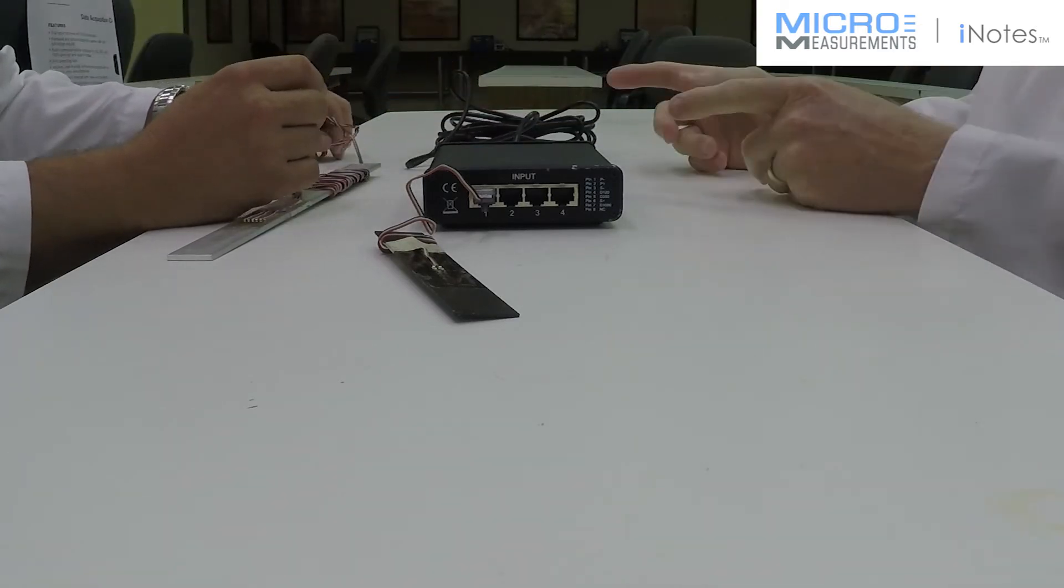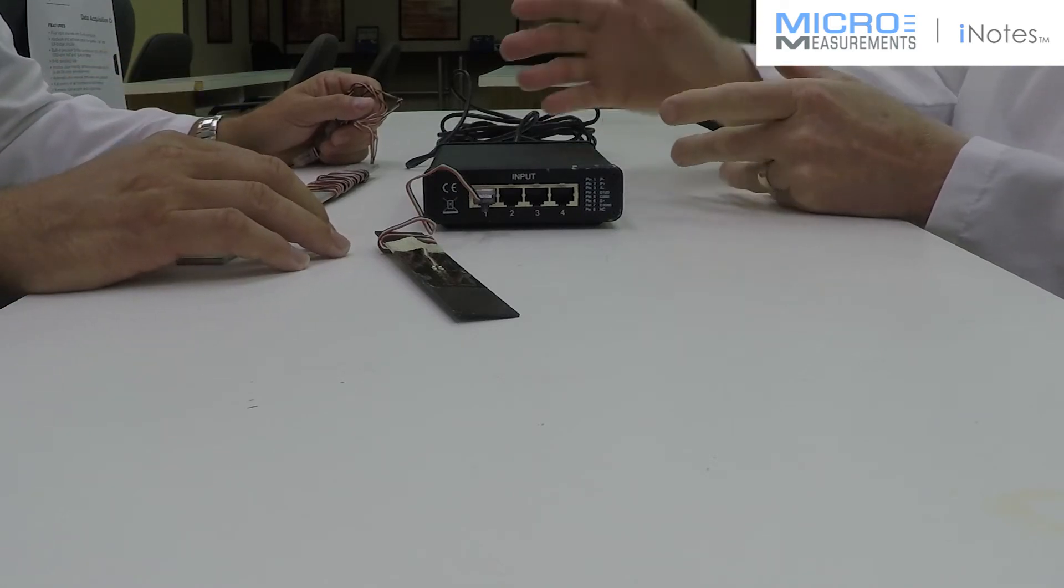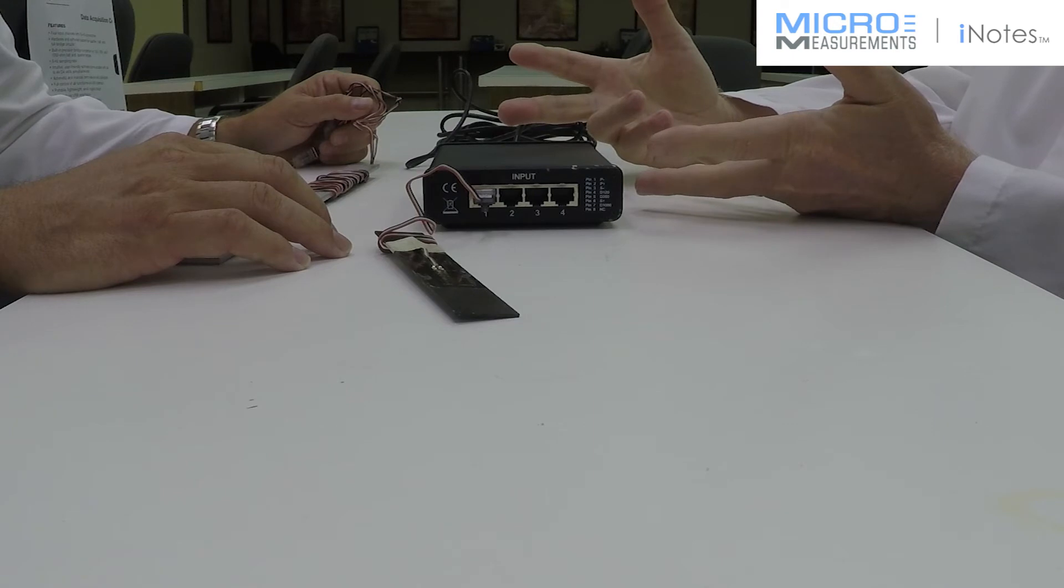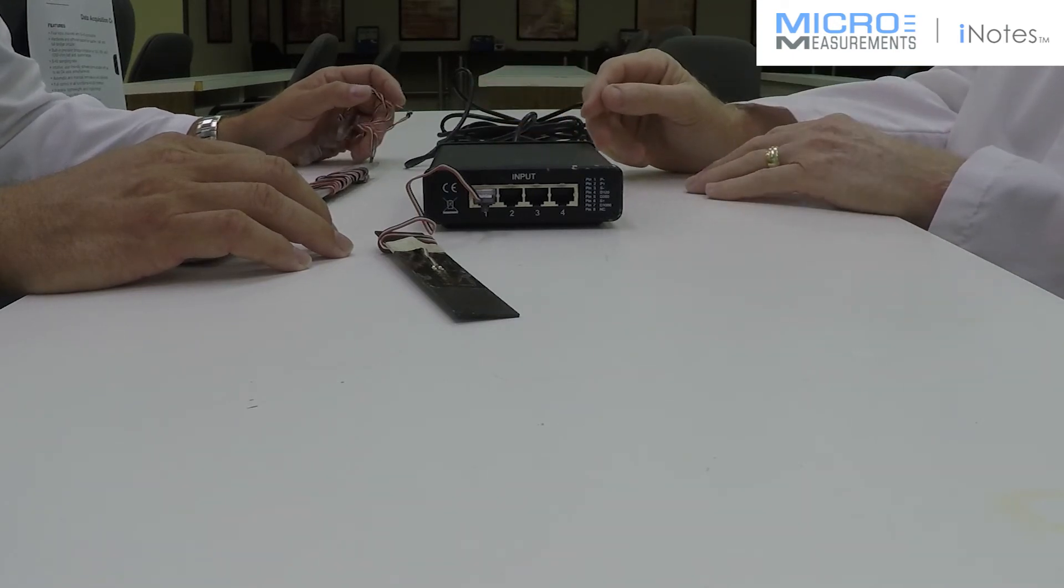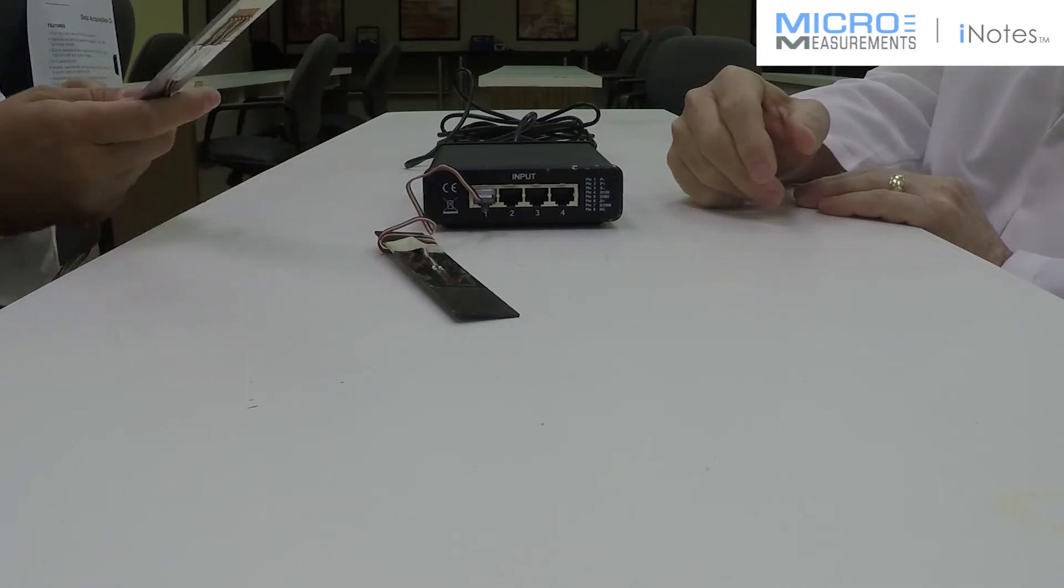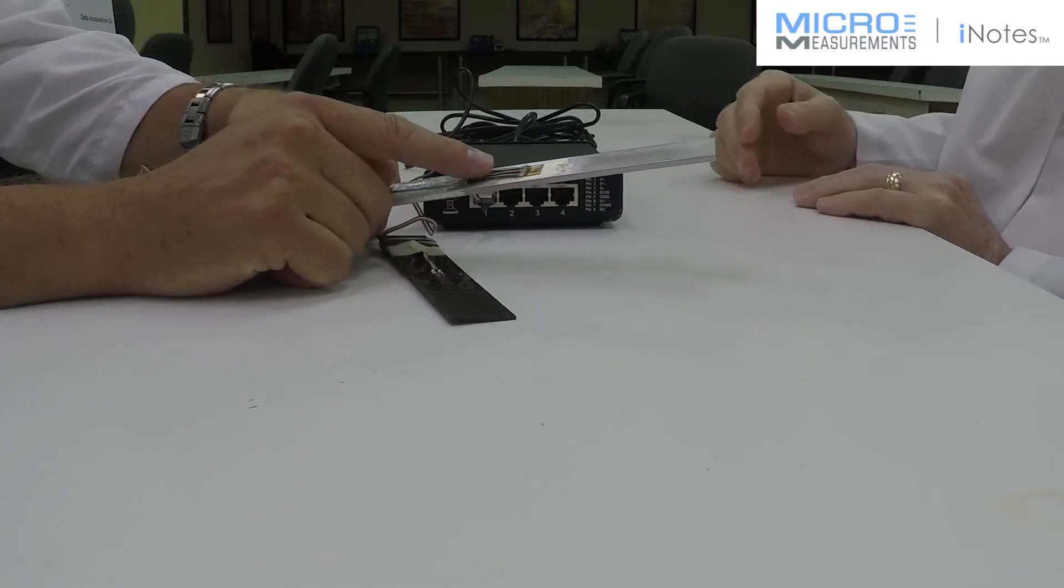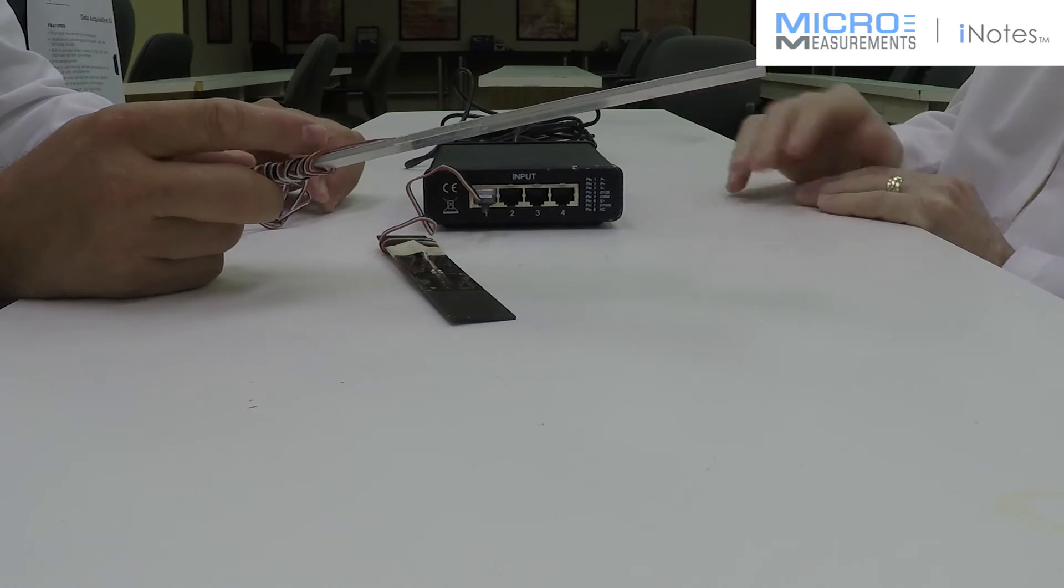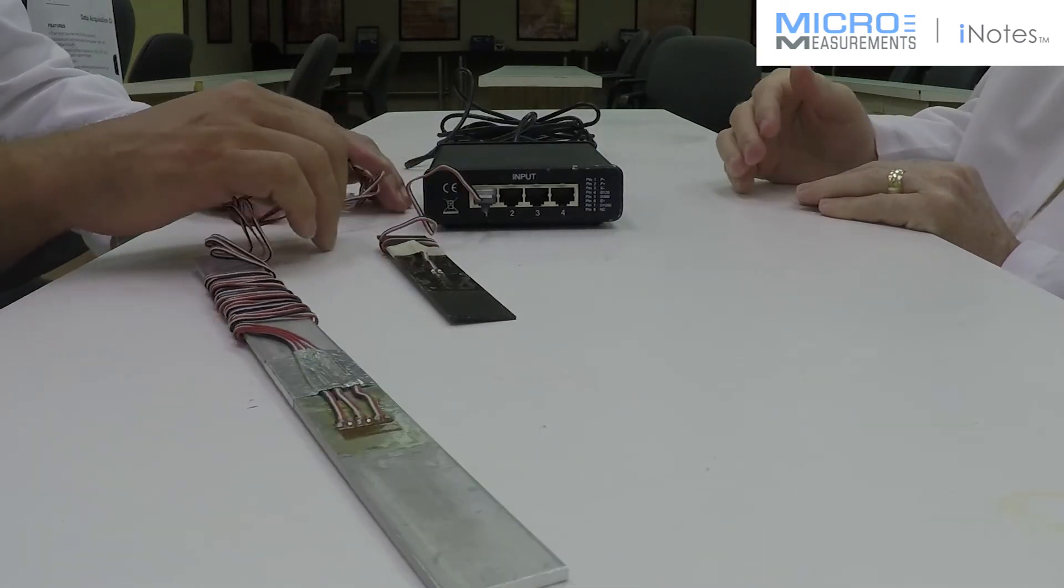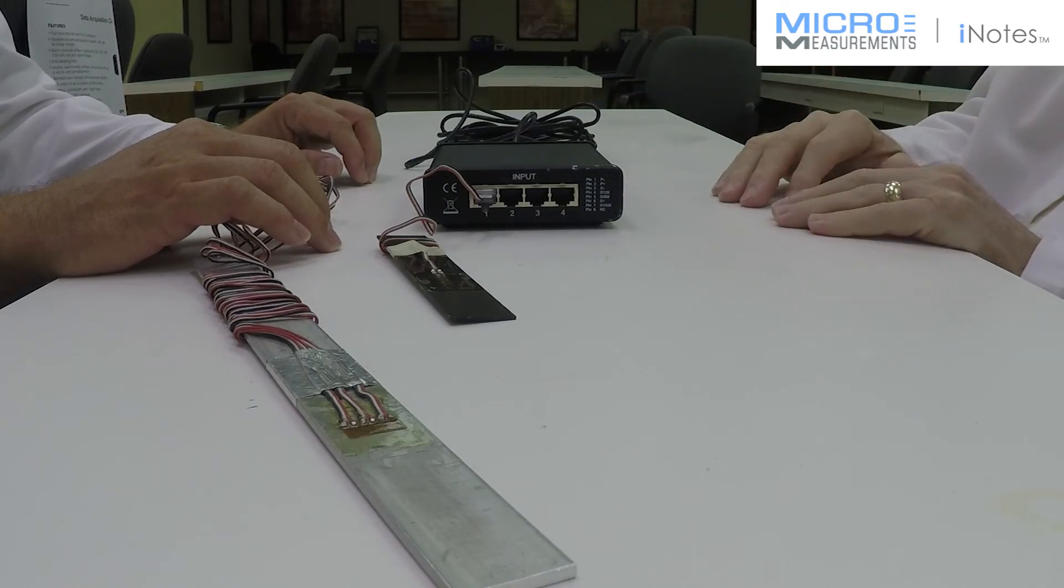And another thing that's nice about it is the software can actually read up to six of these simultaneously, so you could have up to 24 channels of data running simultaneously. And you can also connect a three-element rosette like this one, where you've got three sensitive grids. One box has four channels, right. So you can connect a rosette to it and read each of the elements separately.